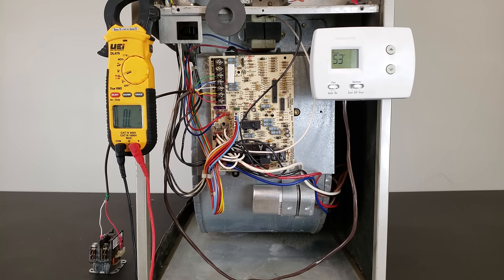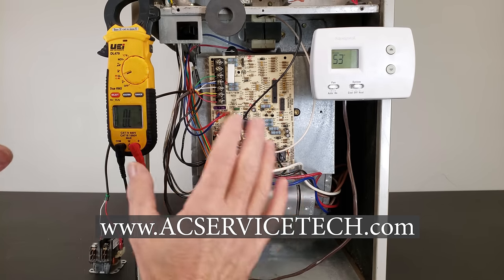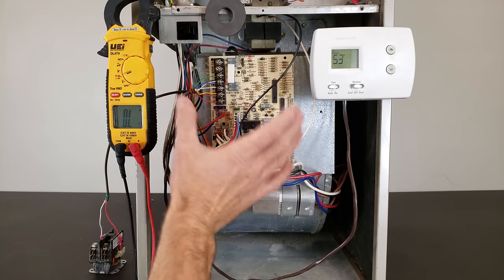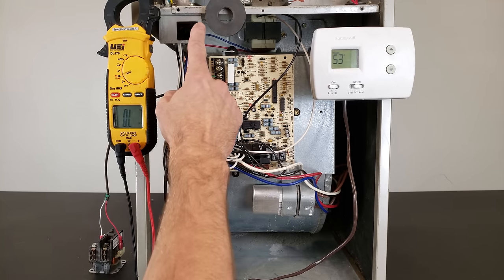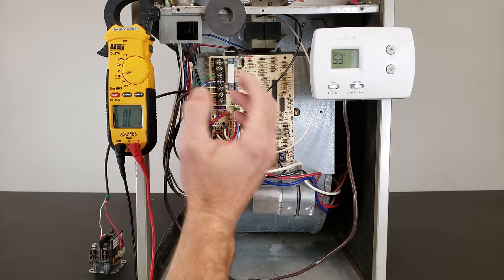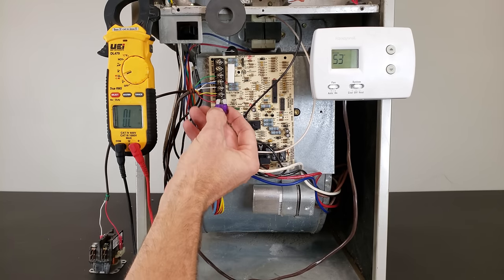Hey guys, this is Cremi Gliaccio from AC Service Tech and today we're going over how to quickly trace out a low voltage short on an HVAC unit. This is a gas furnace right here, we have the power disconnected here and up at the switch. When you have a low voltage short, your fuse — either a 3 amp or 5 amp — keeps blowing.